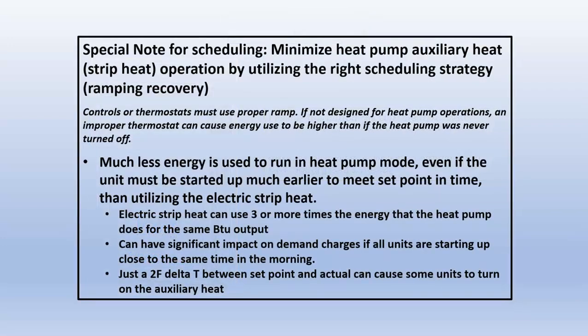Special note for scheduling. You need to minimize the heat pump auxiliary heat operation. You've got to use the right scheduling strategy. What do I mean by that? If you do not use a heat pump ramping schedule, or if you don't use a setup or an algorithm that's set up for heat pumps, you can shut that heat pump off all night long. And if it's too cold in the morning, you will erase all that savings and more when you turn it on, because it's going to go straight to auxiliary heat, which uses 3 times the power that the heat pump does. So sometimes it makes more sense to run that heat pump even all night than it does to run that strip heat.